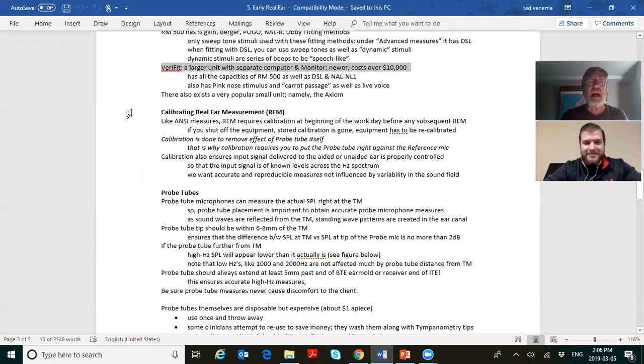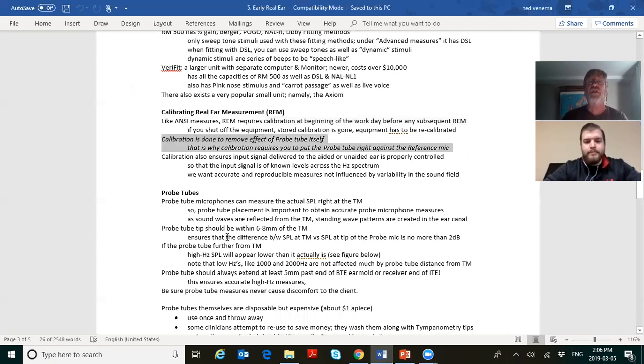Calibrating the system is done first thing in the morning, at the beginning of your work day. Sometimes you can choose to have it hold its calibration for a week. I don't know if there's any advantage or disadvantage, except that a daily calibration is a bit of a pain. But remember the reason you're doing calibration in the first place. It's done to remove the effect of the probe tube itself, and this is why calibration requires you to put the probe tube right against the reference mic, hold that right where the client's face is going to be, 18 inches away from the speaker, run the system, and then look to see that you got the right result. Your equipment will tell you what's a pass and what's a fail.